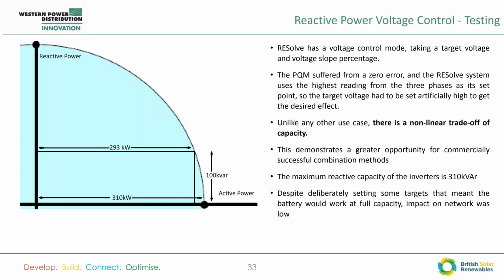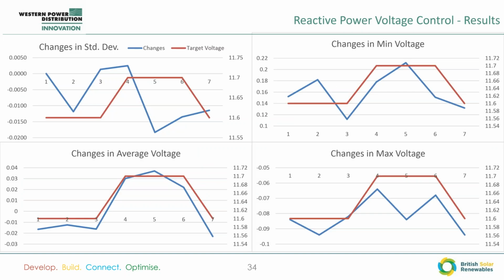So that non-linear trade-off means a slight derating of an asset can start helping a network either adjust its voltage or potentially improve its power factor if there's other influences at play that cause it to be lower. So this shows an opportunity for multiple assets working together, each giving up a tiny amount of their capacity to be able to support the network, and thus the opportunity cost is very low, and therefore the opportunity to help is greater.